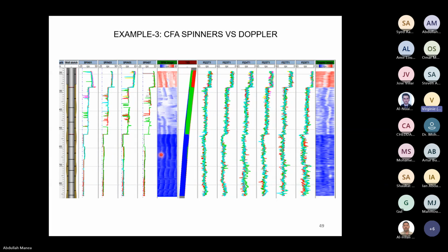So we have around 32 frequency channels currently, and if, let's say, we want to have 1 meter a minute granular resolution, we need to set up the max speed for 30 meter a minute. And in this present survey, if I remember, the maximum frequency was quite high, so that's why maybe we don't see really low flow, because we are setting up the maximum frequency quite high. So we can change that.